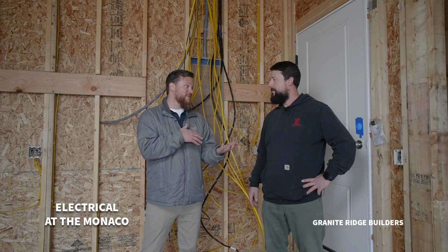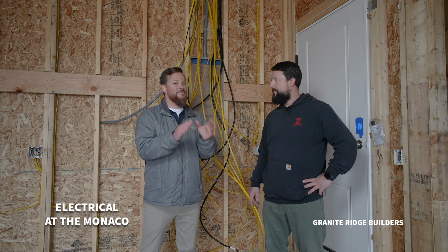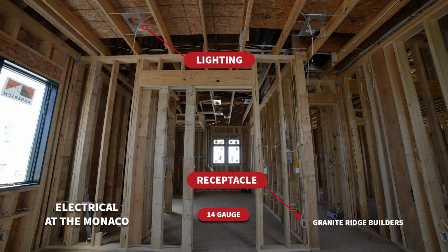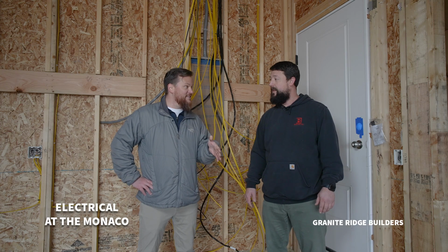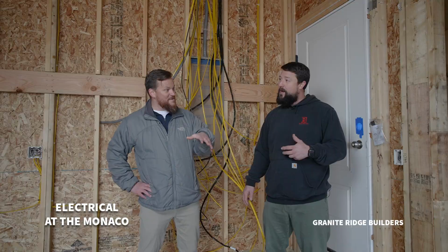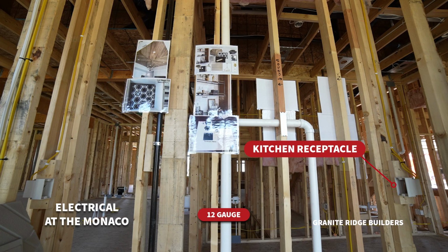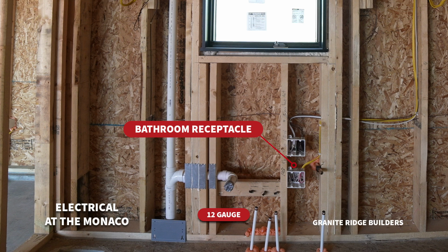So you mentioned the 14 gauge, what would we typically be using that for in a house? So typically 14 gauge would be used for lighting, bedroom receptacles, and that's generally about it. Then 12 gauge is going to be more great room, kitchen receptacles, garages, bathrooms, those that take a higher demand for their load.